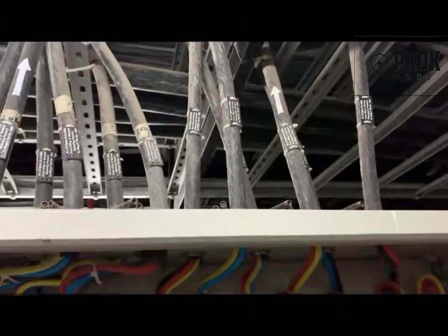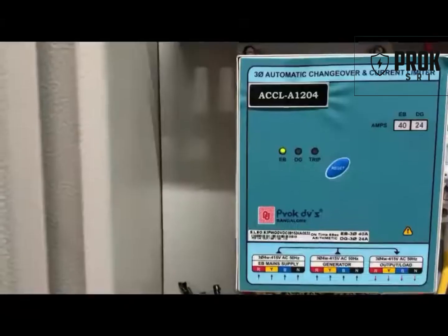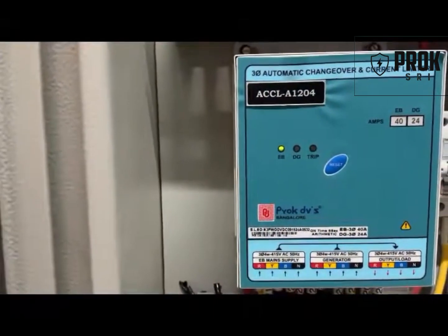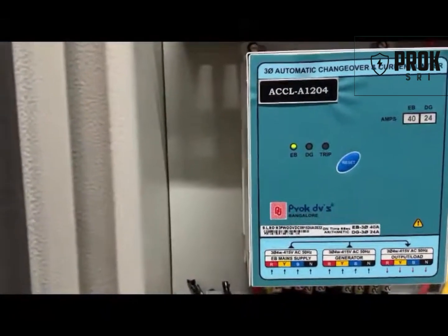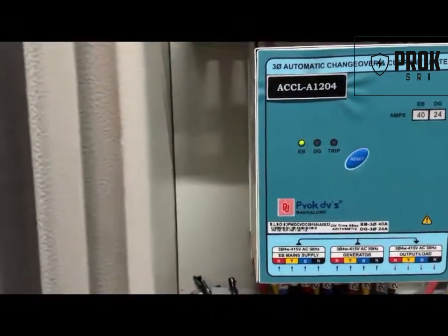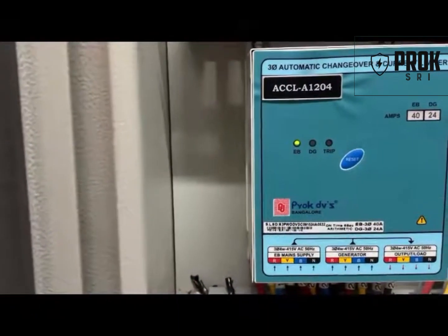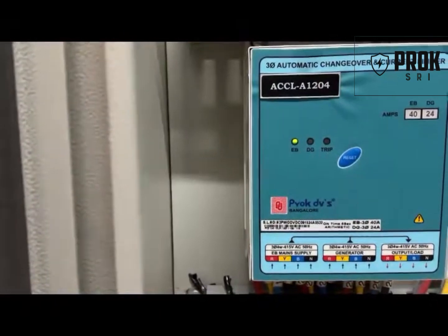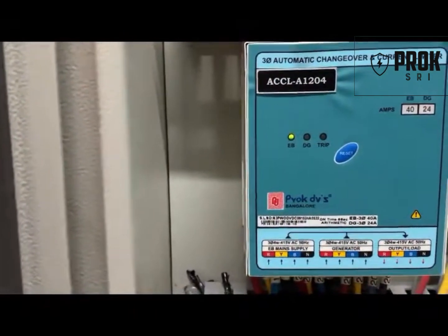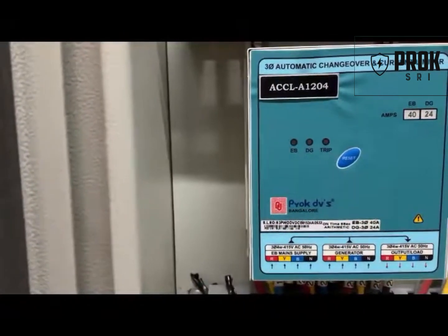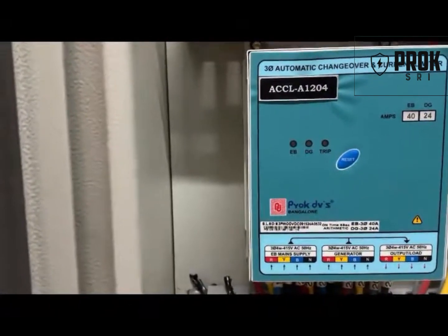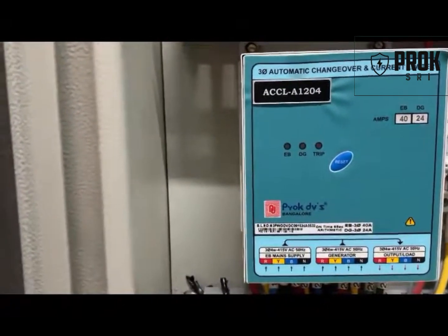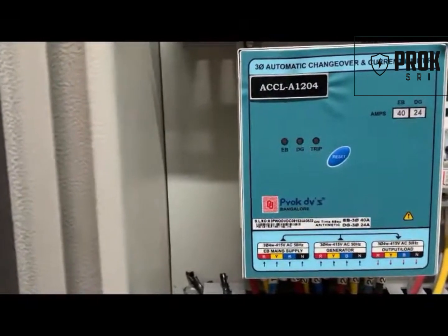Operation of the ACCL. We are going to demonstrate the working principle of the ACCL. Now you can see the EB LED on the ACCL glowing at the moment. We are going to simulate a power failure on EB, and you will see that after a few seconds, the DG LED glows, which indicates that an automatic changeover has taken place.